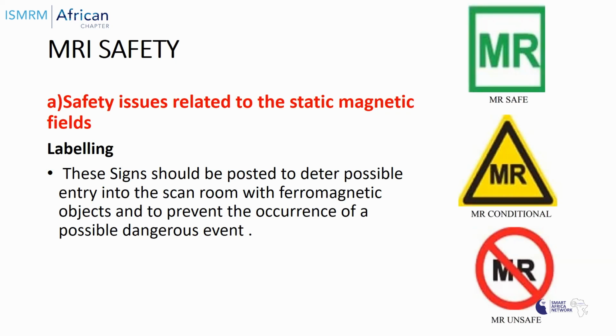These should be posted even on the walls in the MR units, and people should be aware of this, that if the equipment they are having has any of these labels, they need to know what to do. If it's MR safe, then it can go. MR conditional, they have to check the conditions, and the MR unsafe should not be brought close to any magnet.